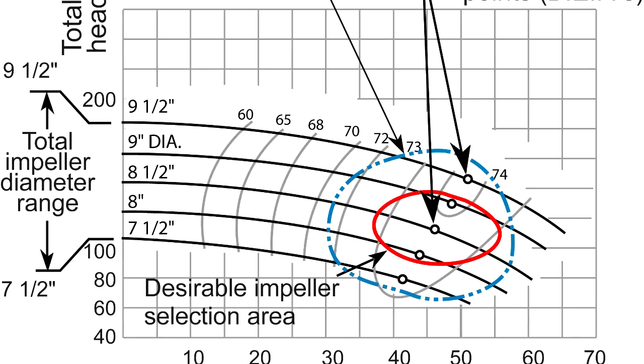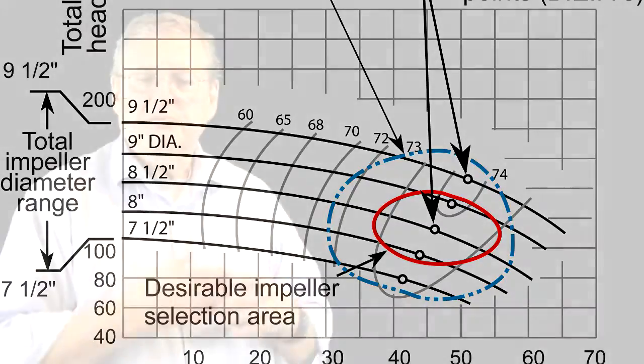Nowadays we're often operating pumps with variable speed drives, so these curves that are showing different impeller sizes would then be curves at different speeds. We get a very convenient ability to change our head and flow by dialing up the speed on the variable speed drive.